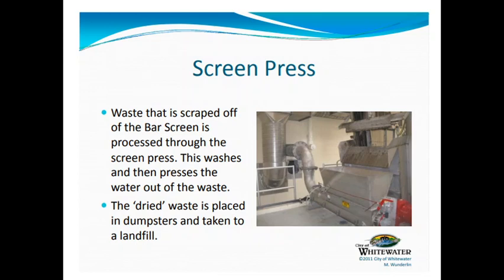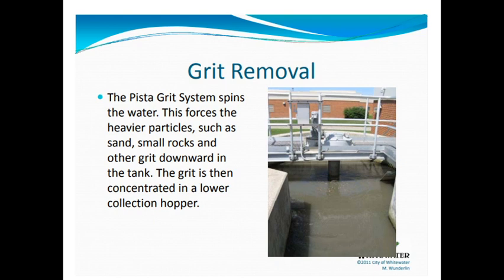They scrape off all the stuff that collects on that bar screen, put it in a dumpster, and take it to a landfill. The next thing that happens is they spin the water, kind of like in a centrifuge. What that does is all the rocks, sand, and grit get pushed outward and downward and gotten rid of, so they don't have to worry about tiny little rocks in the system.